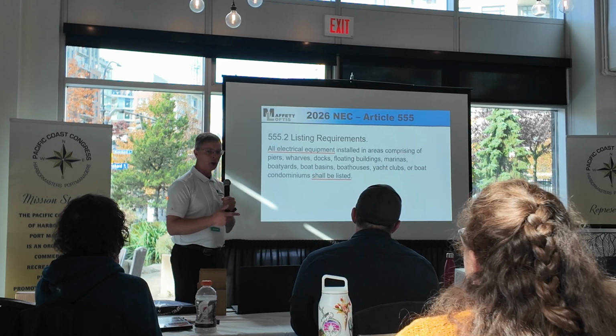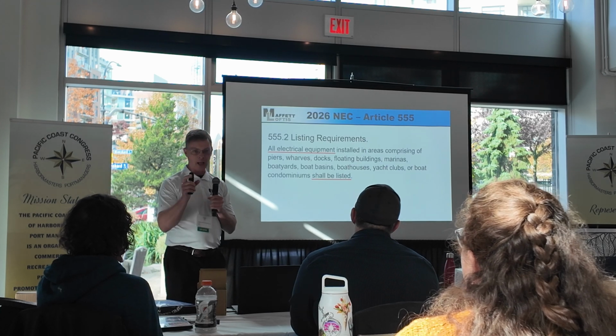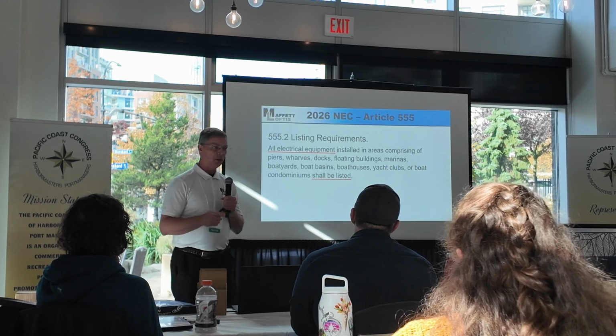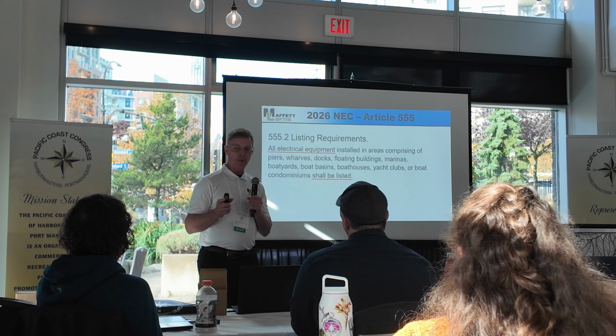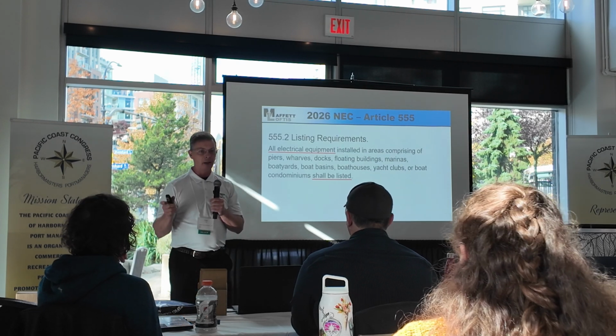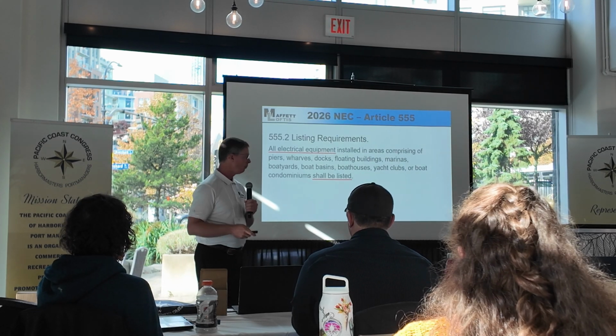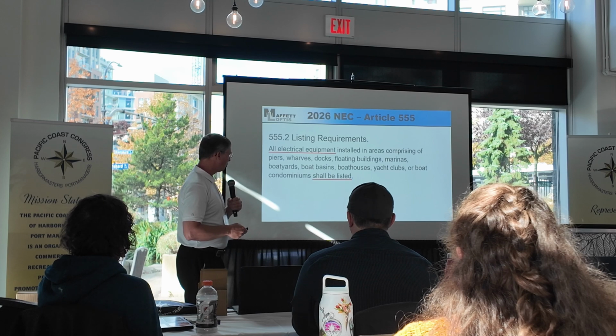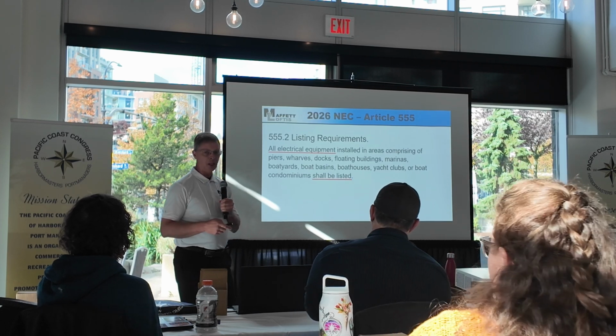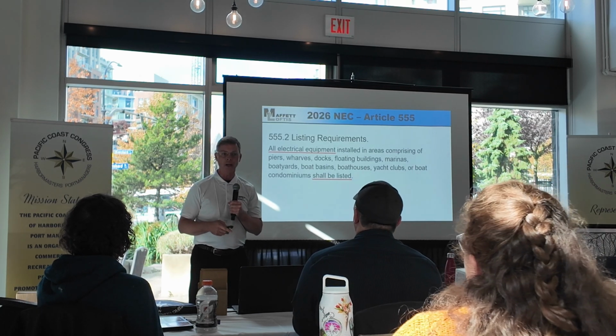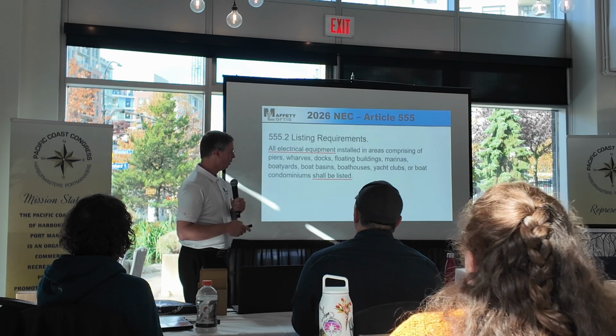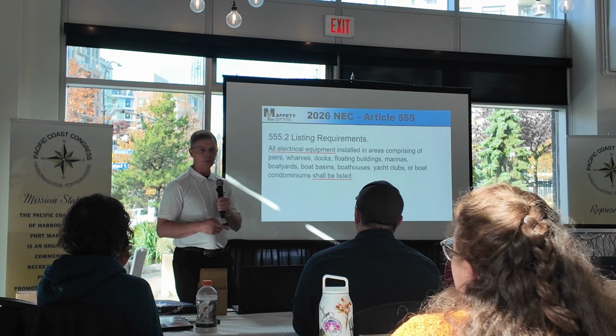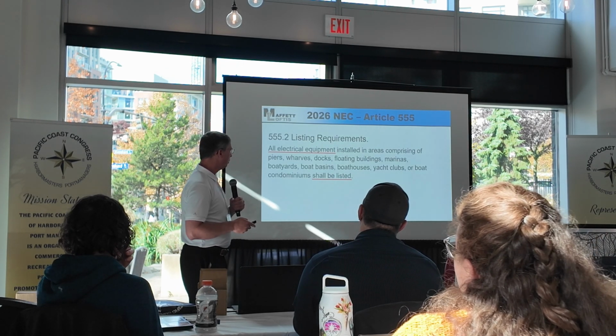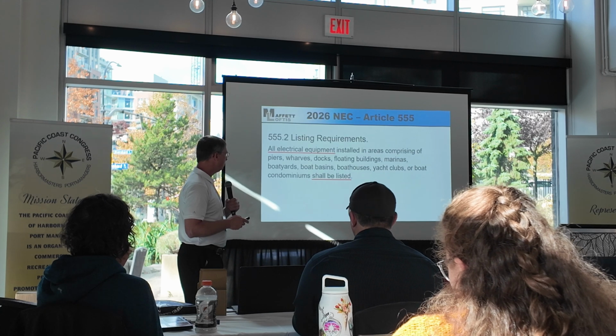And I'm not going to read the code. You can read it for yourself if you want to. I'm just going to highlight some items in it. But every piece, even ground fault protection equipment, everything has to be listed from a third-party laboratory. And there are many approved laboratories out there, so it doesn't have to be UL or one of the ones that we know about. But all equipment has to be listed.